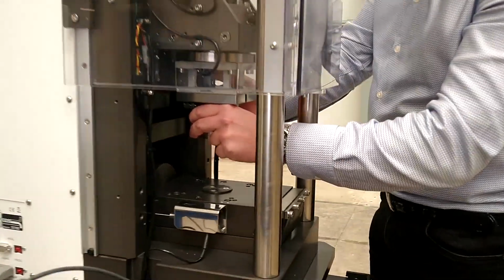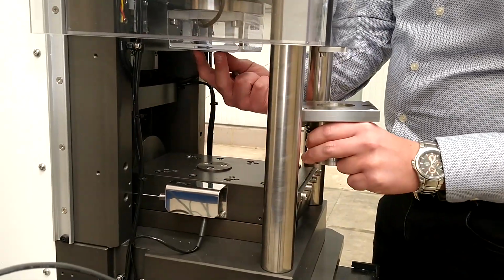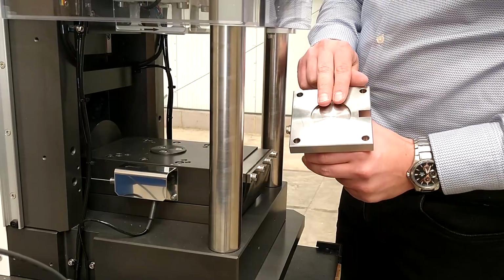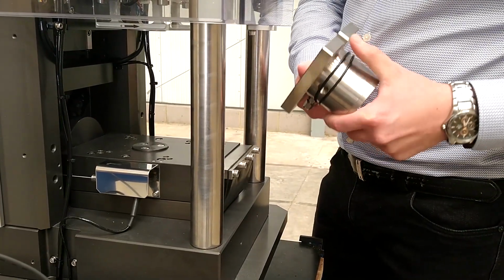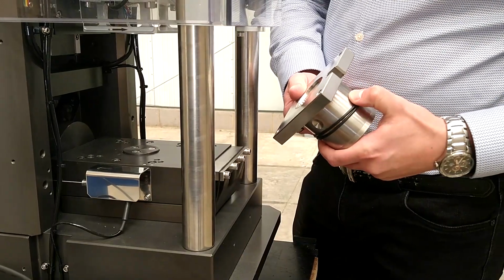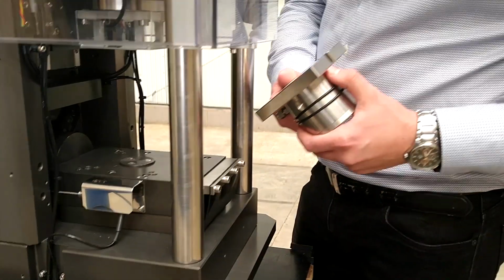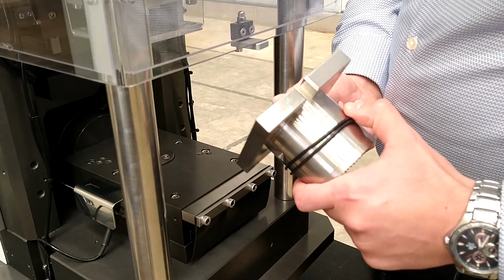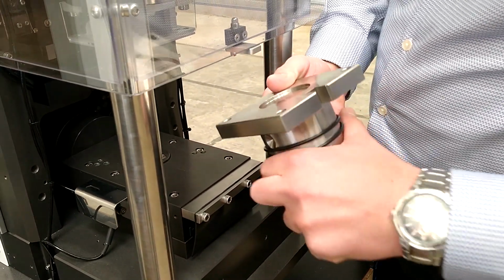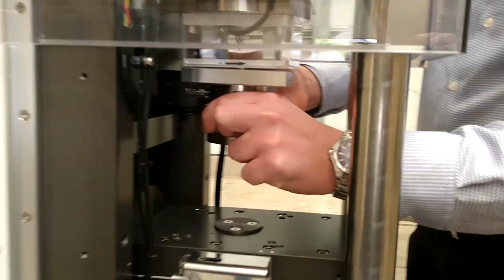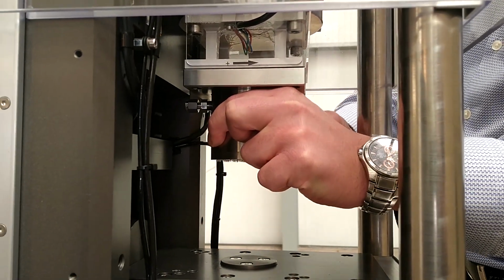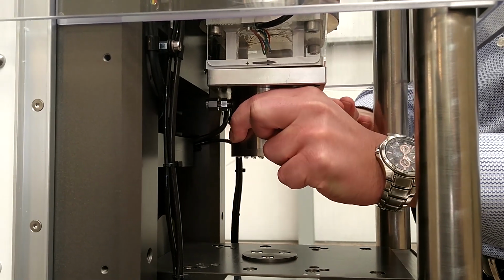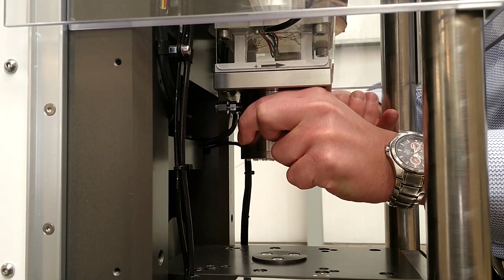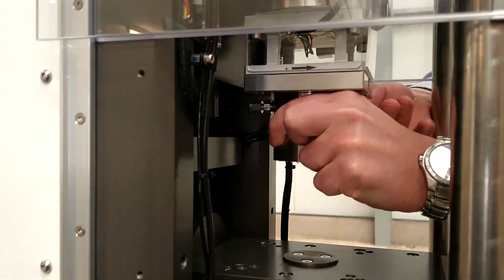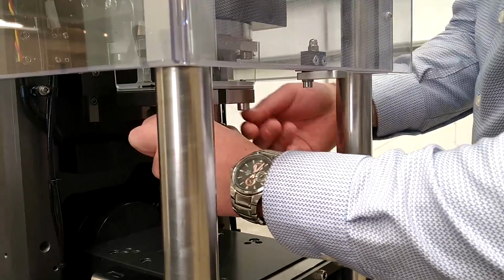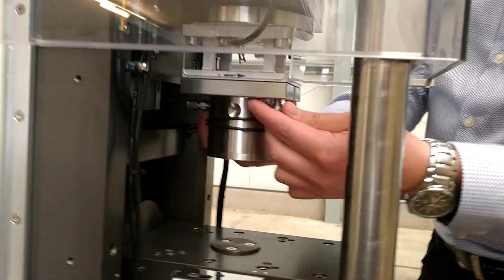So, as you can see, the top cap will lock on the key that is in the load cell and it fits the recess in the top cap. When you're placing the top cap, please make sure the flat part is facing to the front, because that will be used as the target for the horizontal LVDT shear upgrade. So I will lift my top cap, make sure it's tight in the key, and then place one bolt to hold it in place. And now this bolt is holding the top cap.